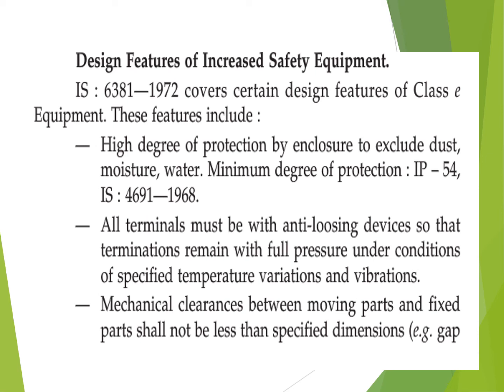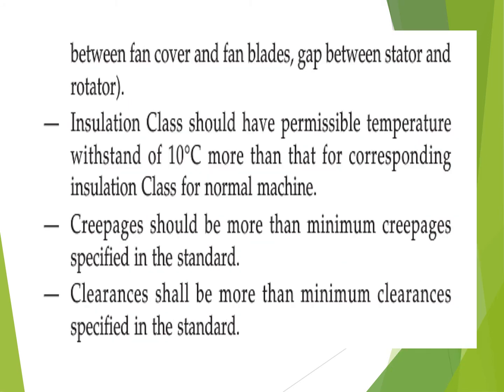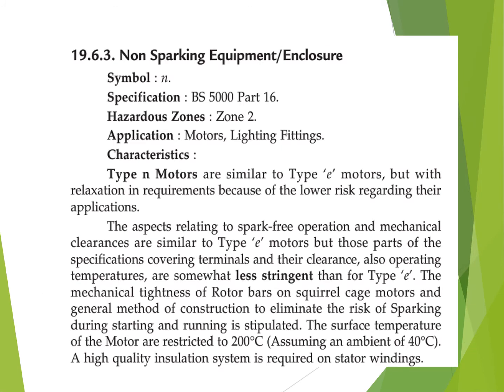Mechanical clearances between moving parts and fixed parts shall not be less than the specified dimension. And the insulation class should withstand the permissible temperature with a margin of 10 degrees Celsius. Creepage should be more than the minimum creepage, and clearances shall also be more than the clearances specified in the standard. Now the next is type N, that is non-sparking equipment.